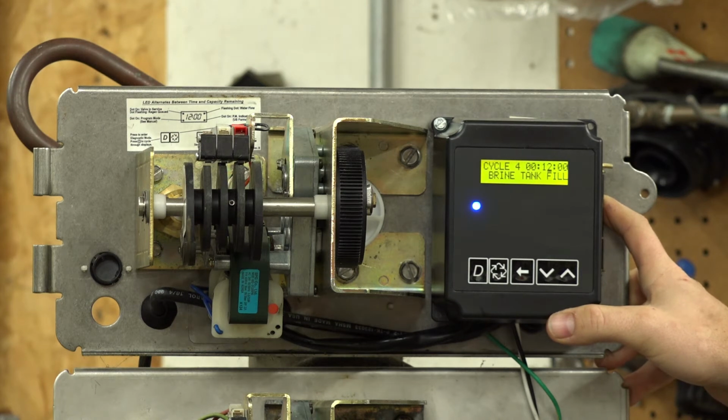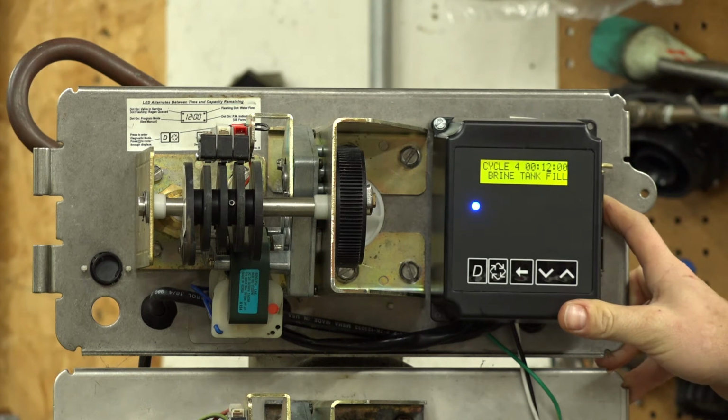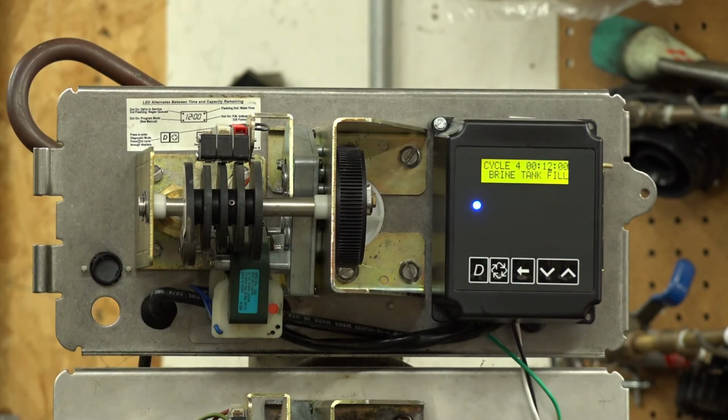Brine tank refill. Now this is going to be where your brine line flow control comes into play. Brine line flow control is going to be on the left-hand side here, coming off of your brine valve. If this is on a smaller valve, it will be printed right on your brine valve. On your larger valves, like the 3900, you're going to have an external brine line flow control. It typically is threaded right onto the brine valve itself and will be identified on there with a flow rate.